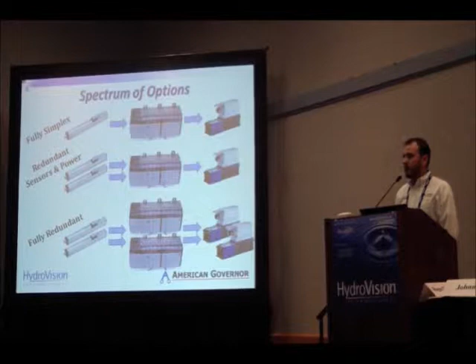These are the simplest and the cheapest to design, the cheapest to implement and maintain. So therefore, you'll see that with the minimum number of components required, you'll have the highest mean time between failures. That's good. You'll run the longest before you have a component failure. Because they're simple, you'll have the lowest mean time to repair. They're easy to work on, they're easy to understand. Your normal plant technicians can replace equipment.